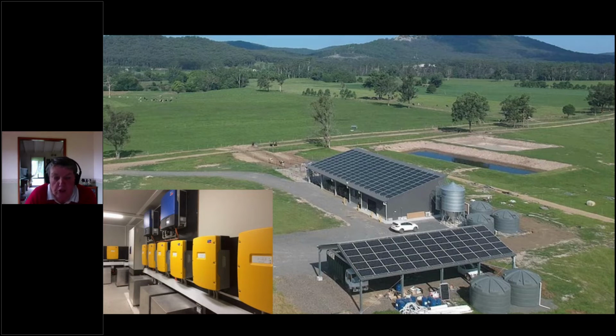Of course, generator use varies according to the weather. In the worst case, with no solar power being produced, the generator would run 4 times a day at 1.5 hours each time, so 6 hours total per day. Best case scenario is no generator use, which is quite common. Over the almost 2 years of operation, we have averaged a little less than 2 hours per day of generator use.